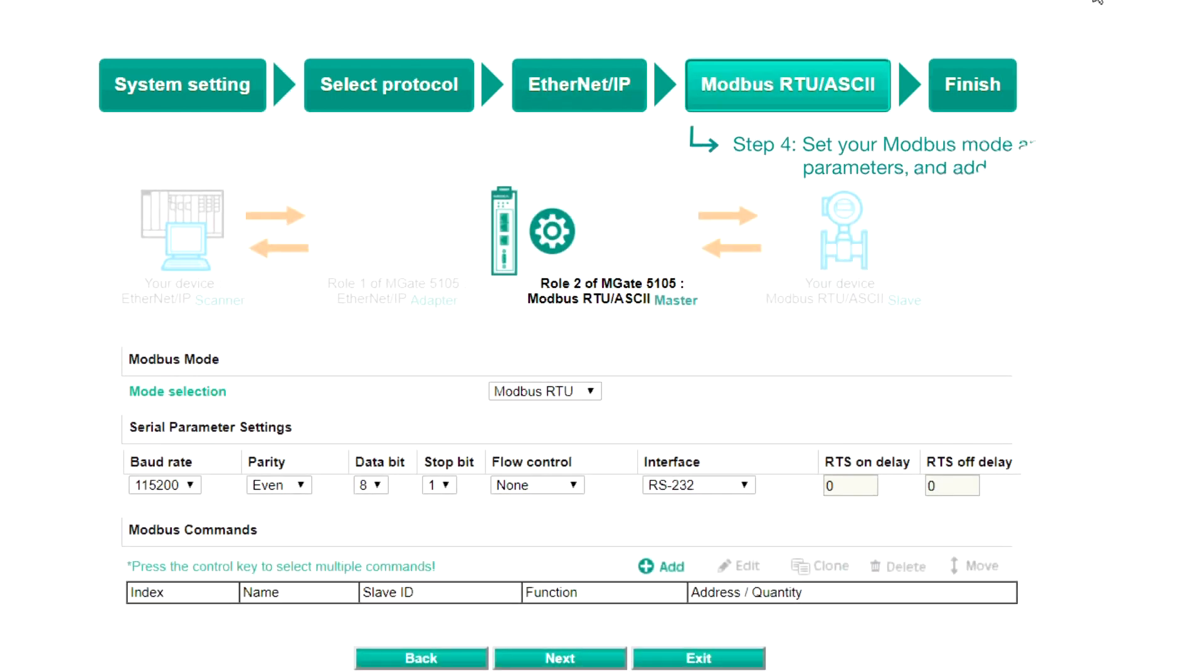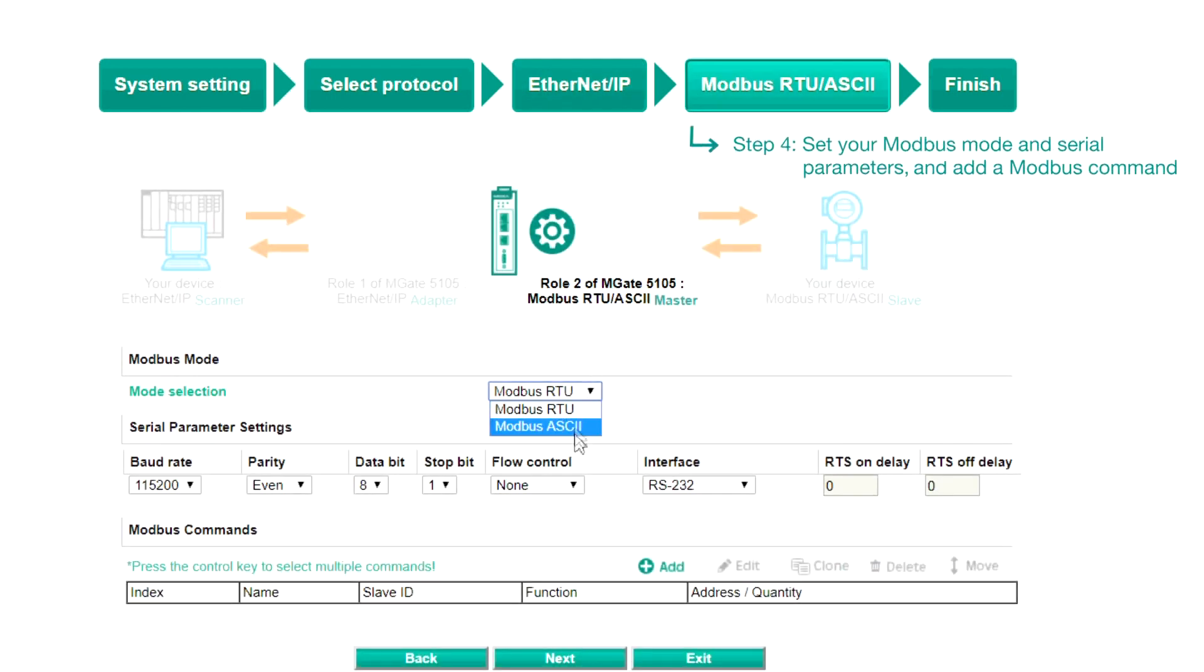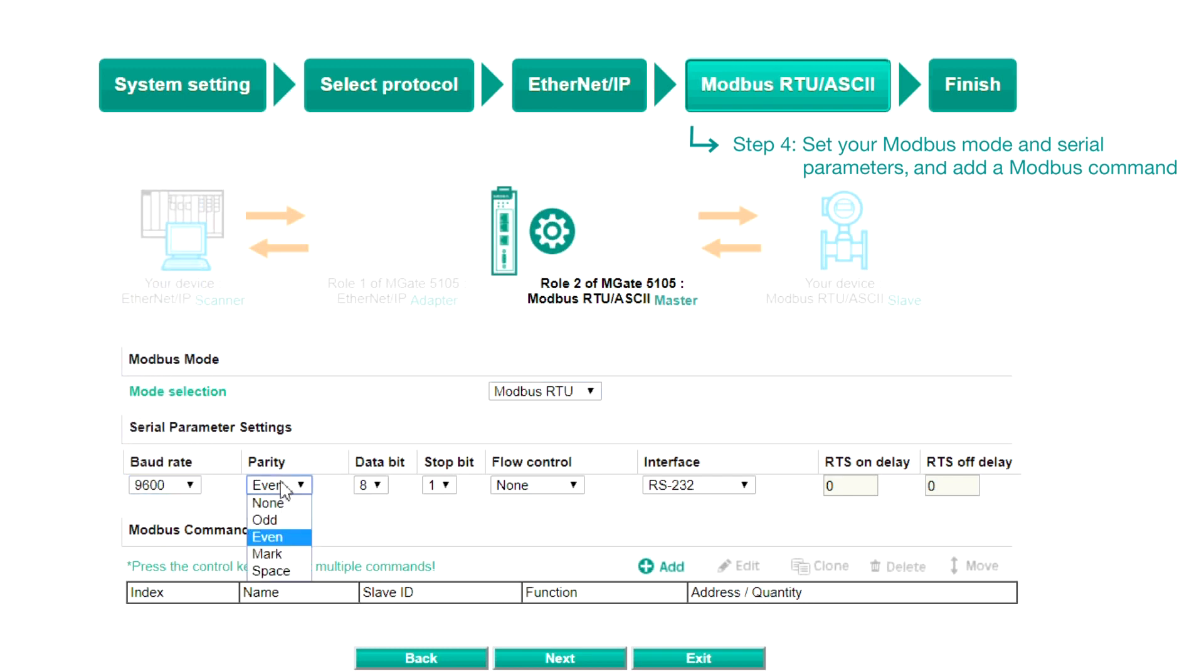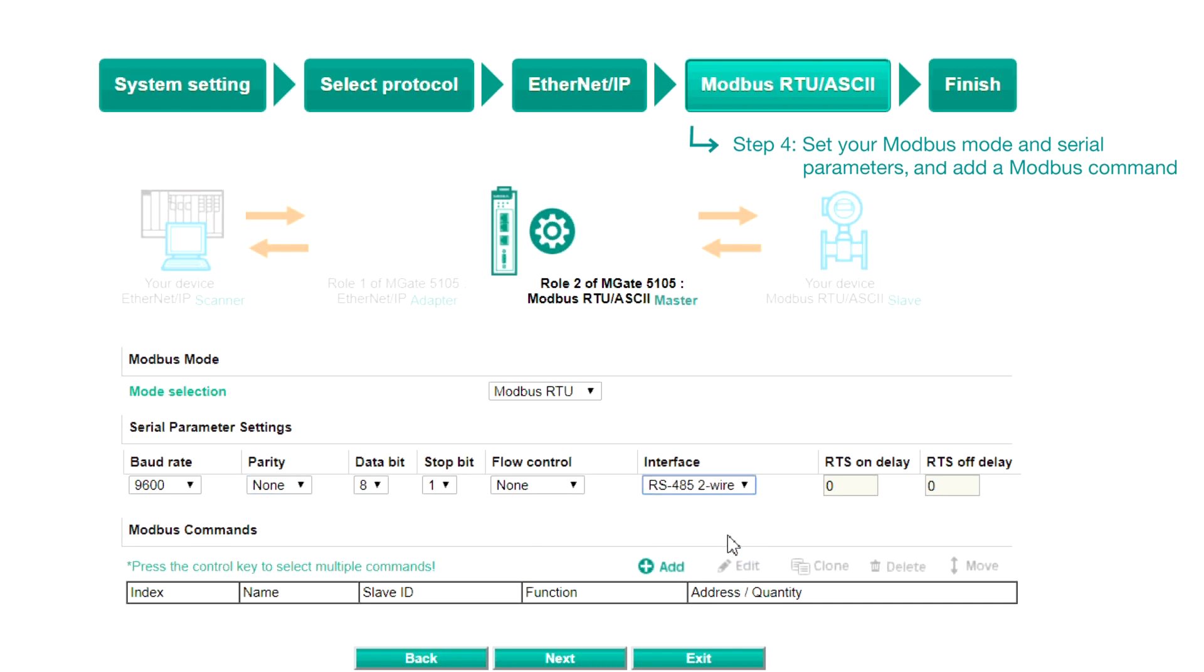Step 4, Modbus RTU ASCII. Select the Modbus mode to use and enter the Serial Parameter settings of your Modbus slave device, such as the Baud Rate, Parity, and which interface to use. To control the speed of the VFD in this demo, we will need to click Add to add a Modbus command.